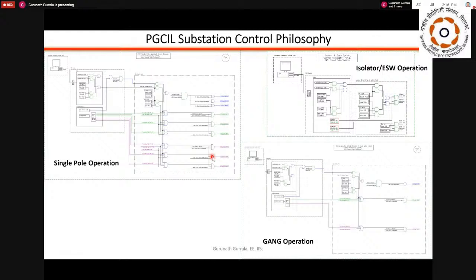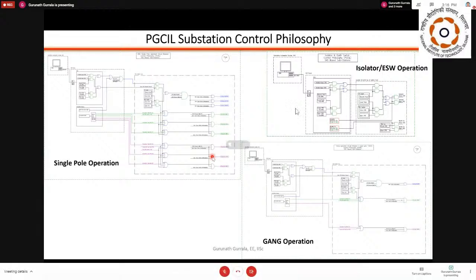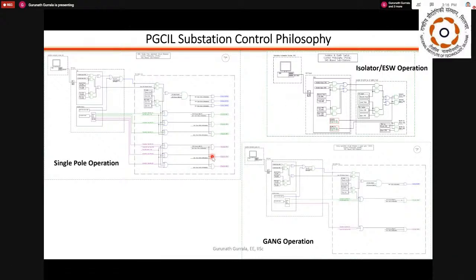These are called interlocks. If a circuit breaker is closed, you cannot open your isolators, because a closed circuit breaker means it is charged and there is a load possibility. So isolators can never be opened without switching off the circuit breaker.